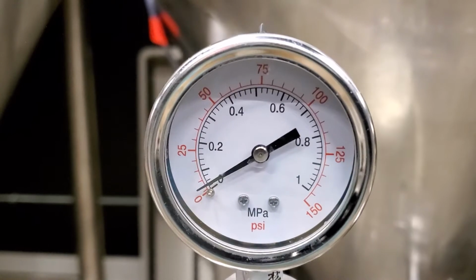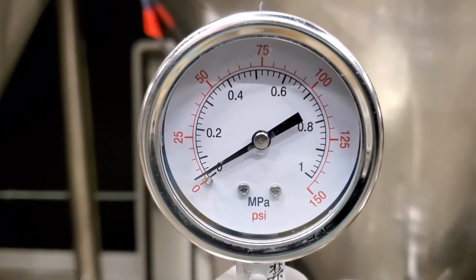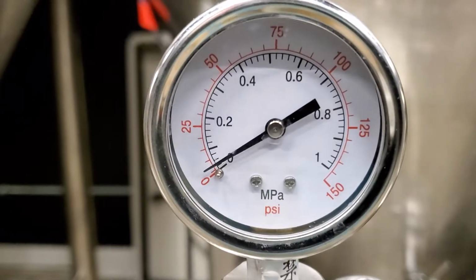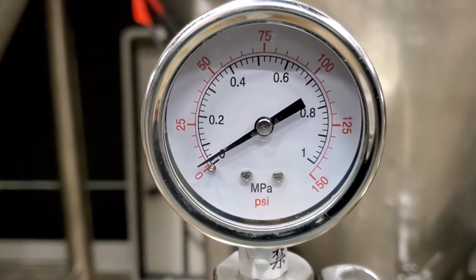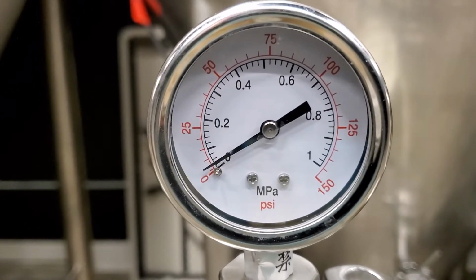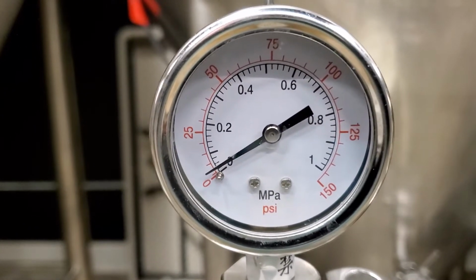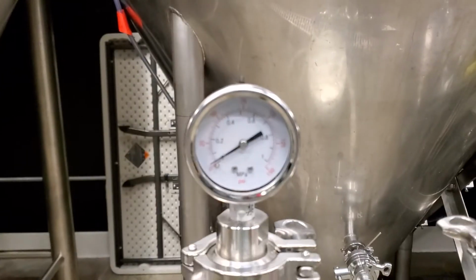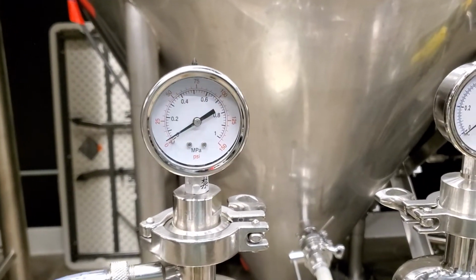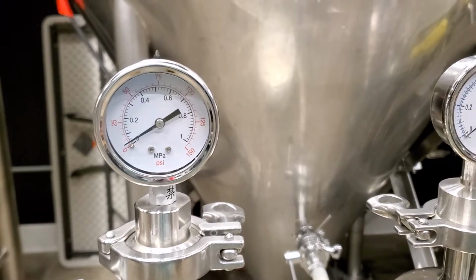If it does get too high, we're going to have to stop this filtration, back flush the system, forward flush it for sterilization, and then start again. That's always something that's kind of a bummer to have to do, but in this particular situation, it's 100% necessary.